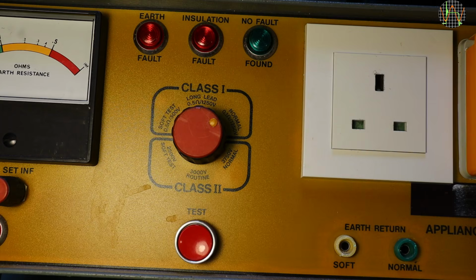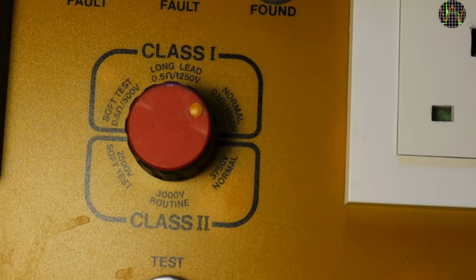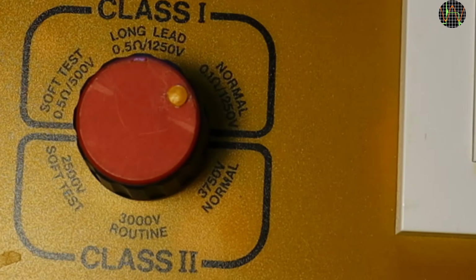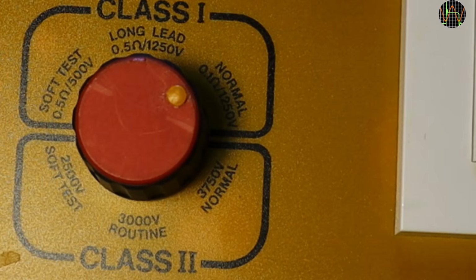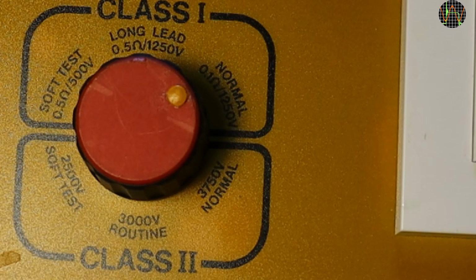In the middle we have a rotary button with 6 positions. The top 3 are for class 1 equipment. Basically that's stuff that has a proper earth connection like a toaster or kettle, and all metal parts should be connected to earth. The lower 3 are for class 2 or doubly insulated equipment like USB chargers that are in a plastic housing and have no earth connection. In either case, the most left position is the soft test and it gets tougher on the other settings.